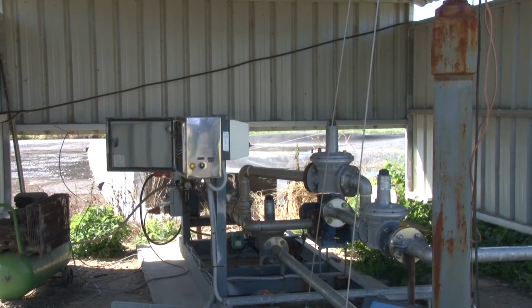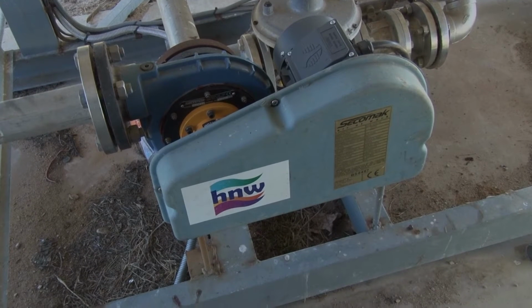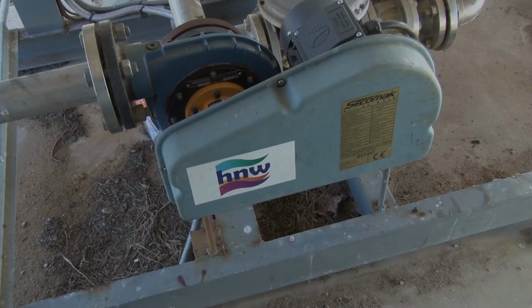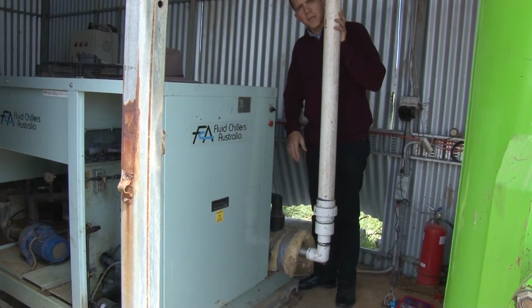Because the biogas pressure under the cover is low, the biogas usually needs to be pumped. Biogas also contains lots of moisture which has to be removed so that it does not extinguish the biogas appliance or restrict the flow of biogas in pipelines. This can be done with an electrical biogas chiller unit.